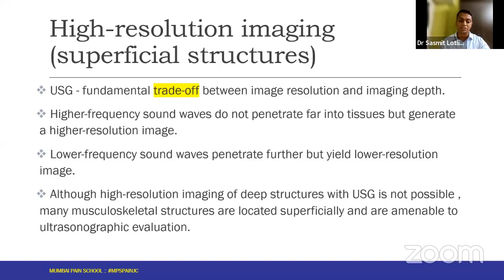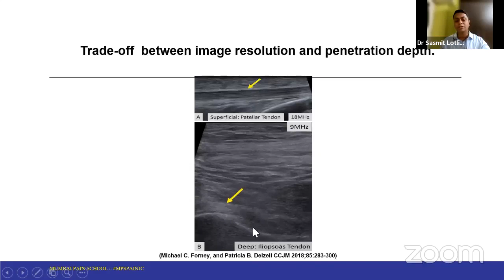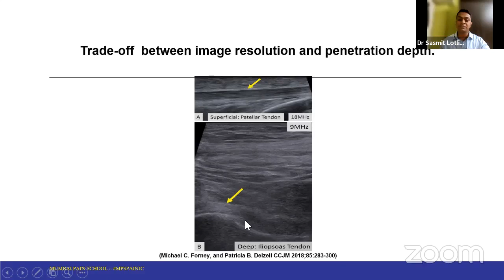If we see this image here, the first image, image A, shows a superficial patellar tendon, and using a high frequency probe, you can see the clarity is very good. So higher resolution with a higher frequency probe, but the depth is very less. Coming to deeper structures like the iliopsoas tendon, a lower frequency probe is used, which can penetrate into the deeper structures, but as we can see, the resolution is very poor.